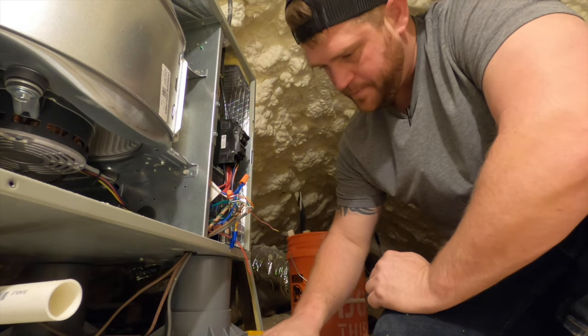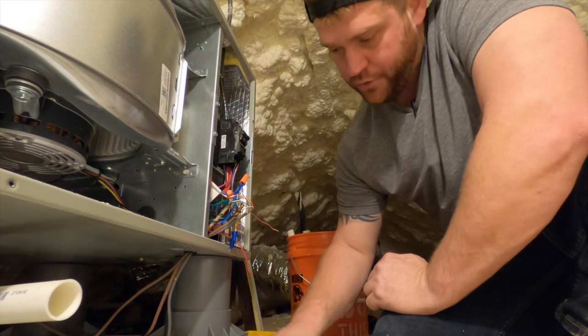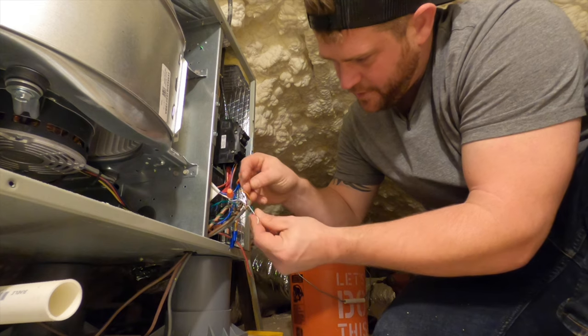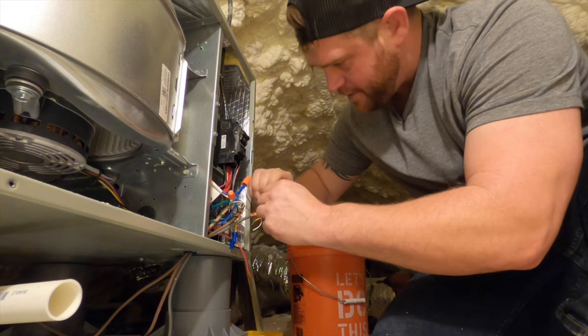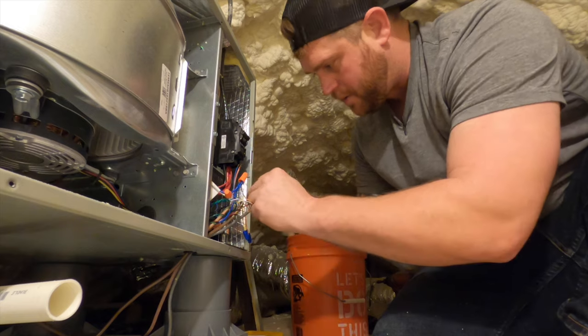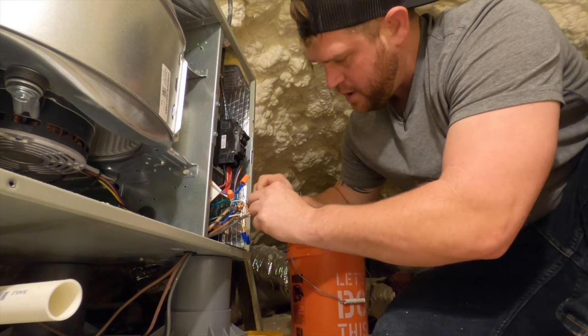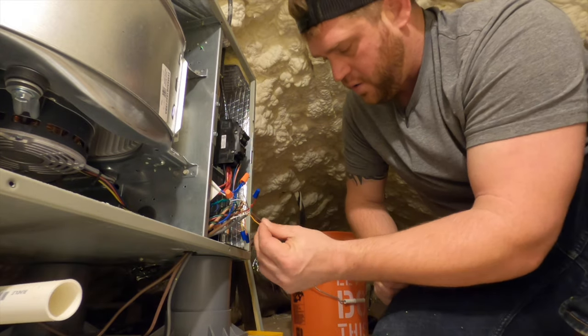On these wet switches, you've got 24 volts of power and then you have a set of contacts. The green is common and the orange is normally closed. The red and the green - which is the common side of the contacts - need to wire together to the 24 volts coming from the transformer. Then we'll break R with the orange, and we'll also run the secondary switch in series with orange as well.